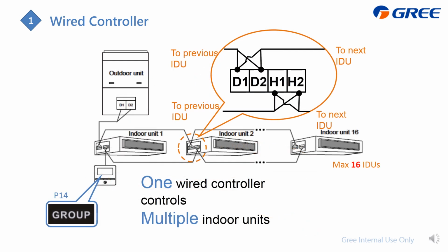As for one wire controller controlling multiple indoor units, the wiring is just like this. They should be connected in series with each other, and the max is 16. The wiring just follows this one. Besides, you also need to set P14 on this wire controller, which sets the group control quantity. It should be the same as the actual situation.